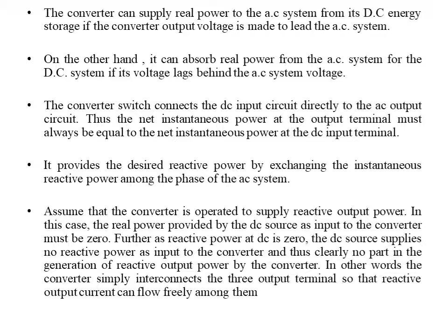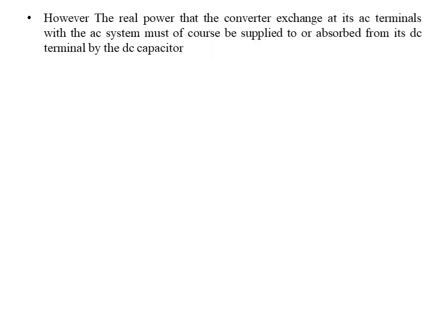In other words, the converter simply interconnects the three output terminals so that the reactive output current can flow freely among them. However, the real power that the converter exchanges at its AC terminal with the AC system must of course be supplied to or absorbed from its DC terminal by the DC capacitor. Here this DC capacitor is connected at the DC energy source. Although the reactive power is generated internally by the action of the converter switches, the DC capacitor must still be connected across the input terminal of the converter to provide a circulating current path as well as a voltage source. So this capacitor acts as a DC source, and it also has a second function, that is, it gives the circulating path for the current.